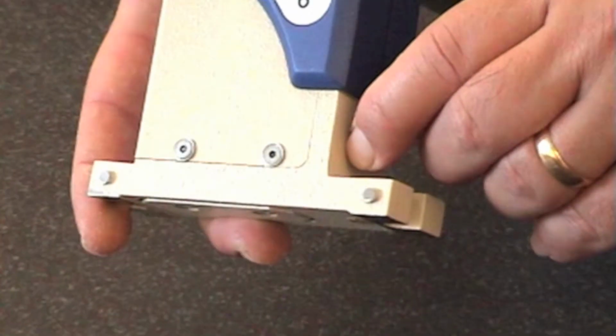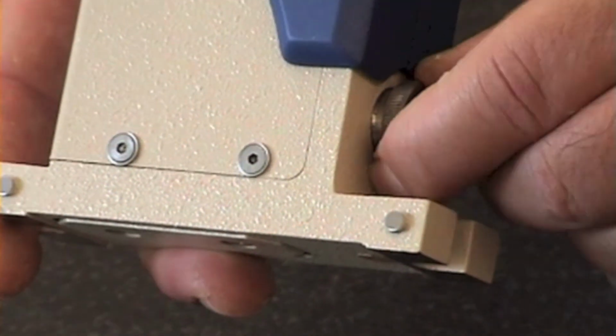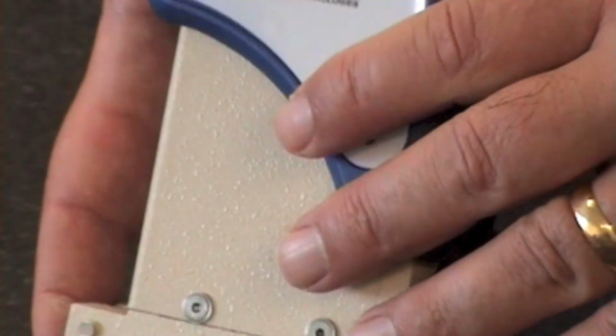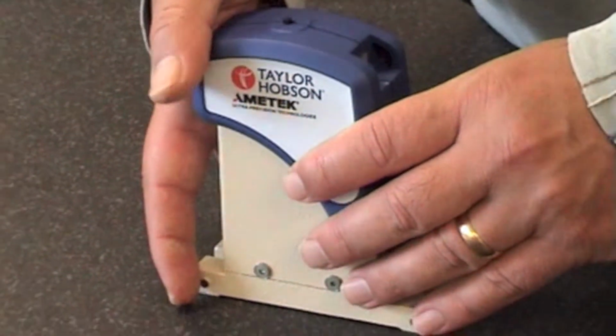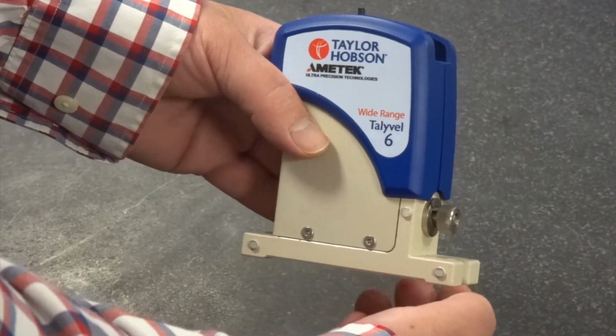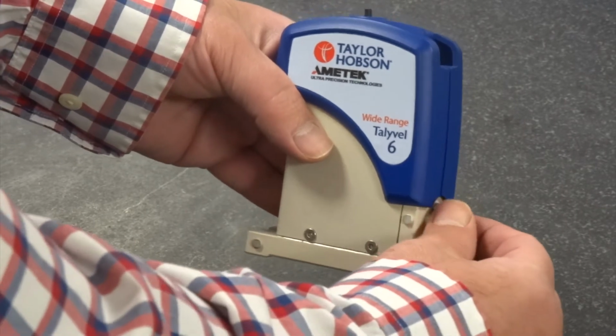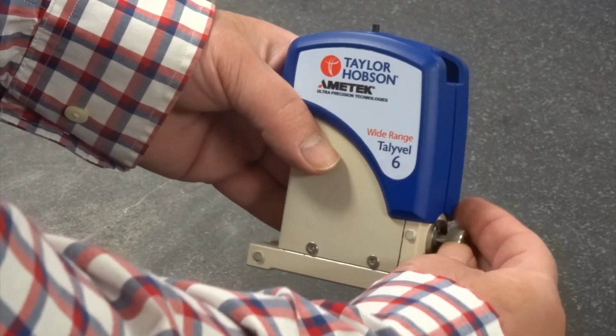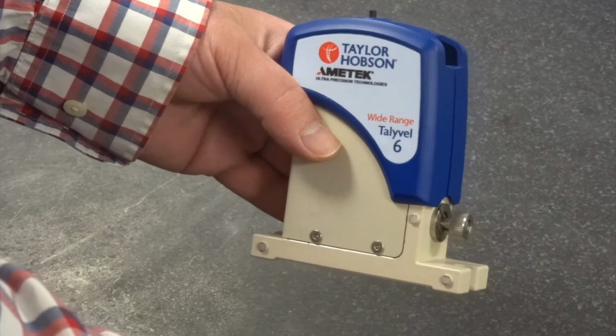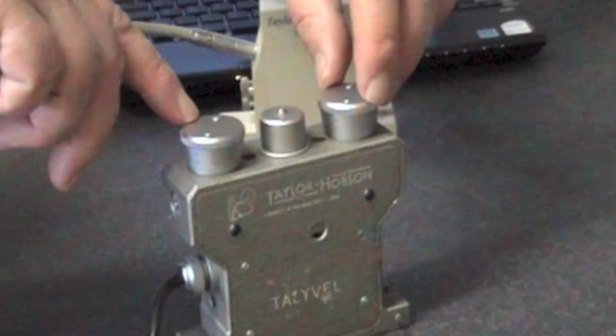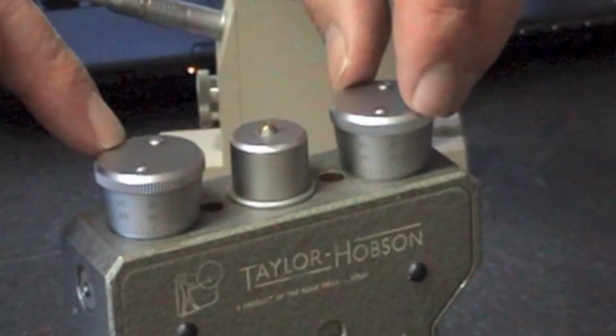The Talyvel is a delicate instrument and there is a clamping knob on the side which needs to be done up during transport and unclamped for measurement. On newer models, this is a simple on-off mechanism. On the old Talyvels, the clamping mechanism was the two knobs at the top.